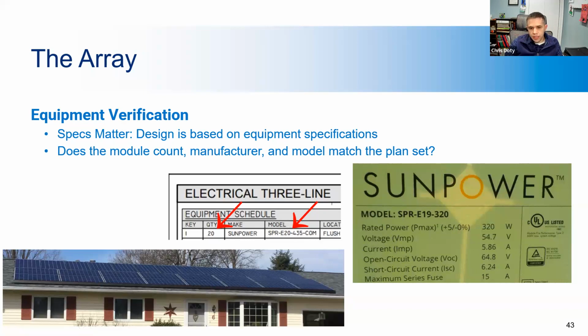And the reason this is so important is because all of the design is based on the precise electrical characteristics of the module, and the string configuration, as well as the inverter's output characteristics. So if equipment is substituted in the field, the equipment could become undersized for the new electrical characteristics. A good example of this is the max system voltage. The open circuit voltage characteristics are higher for higher wattage modules, or even the same wattage modules from different manufacturers. And all of your circuit sizing, overcurrent protection, etc., were designed based on the energy production from the design panels. And you don't want to just assume that the wiring and the system components are still compatible, because they may not be, and you could be overloading the conductors and melting them and causing fire. So that's definitely something you want to take a good look at.